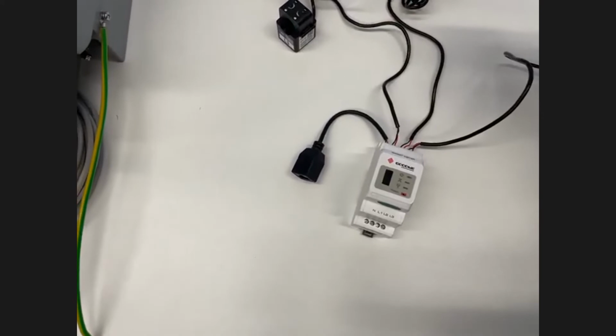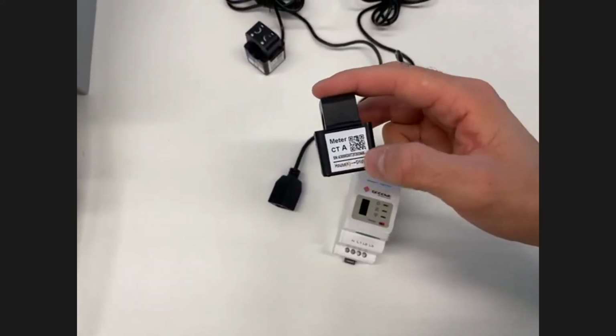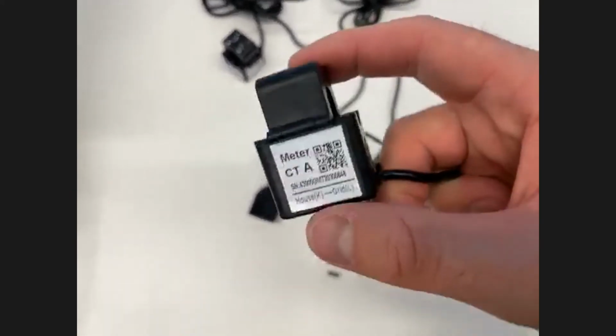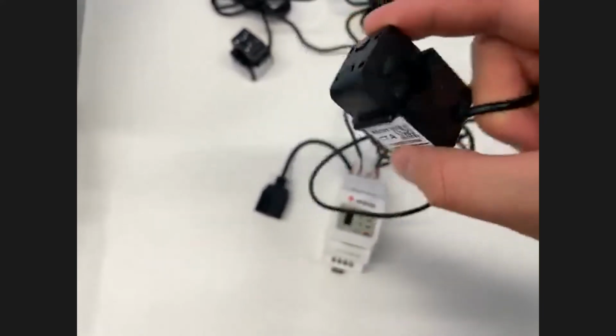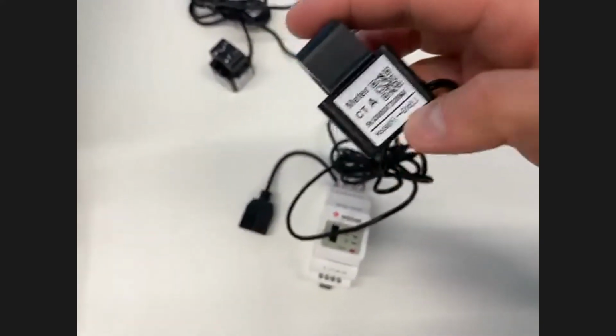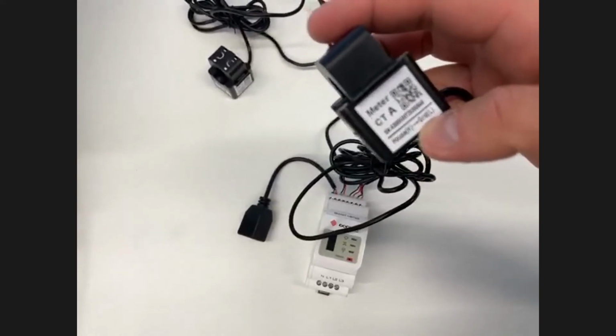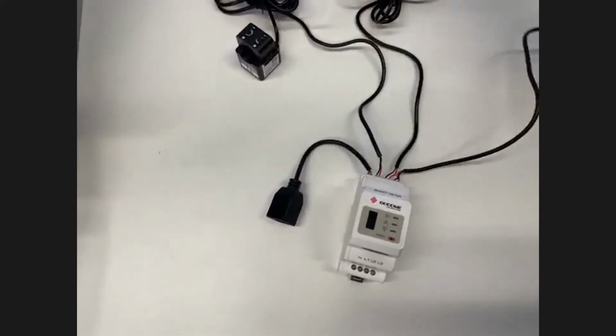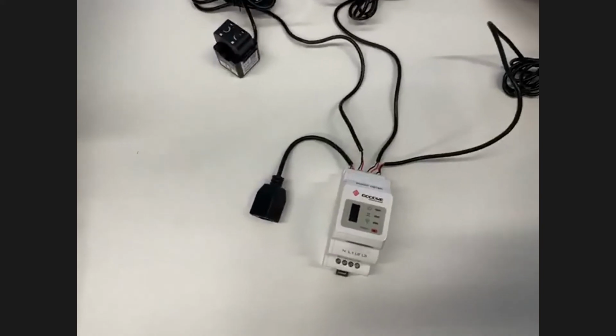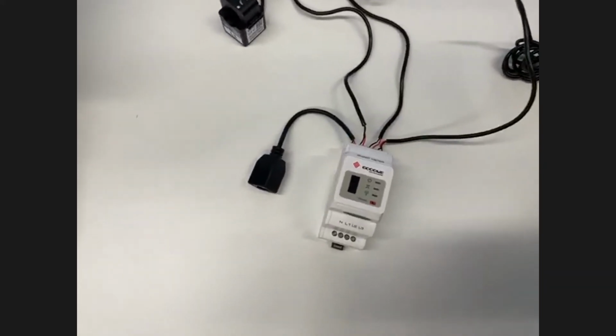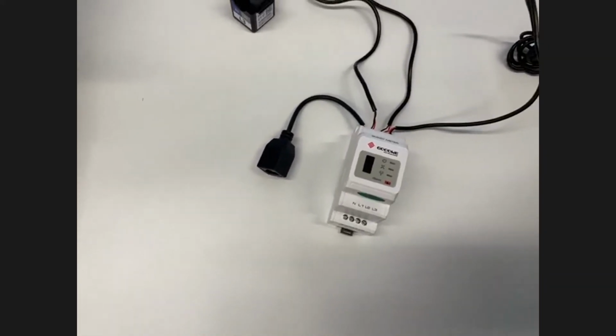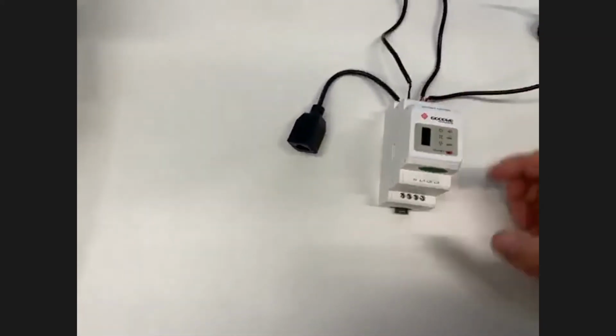So here you have CT A, like this. And you also see here house to grid, so the arrow here should always face the grid. This is very important, especially if you want to use the export limit function. If you have them the other way, they won't be able to limit the export.